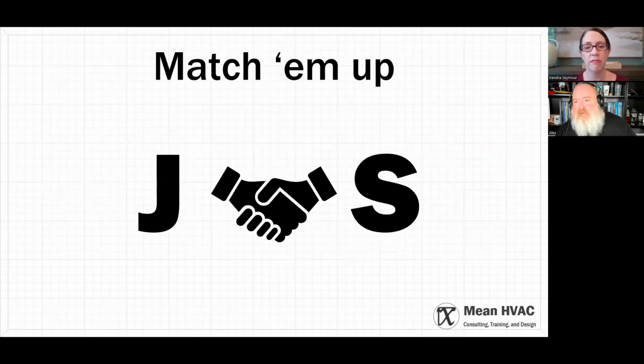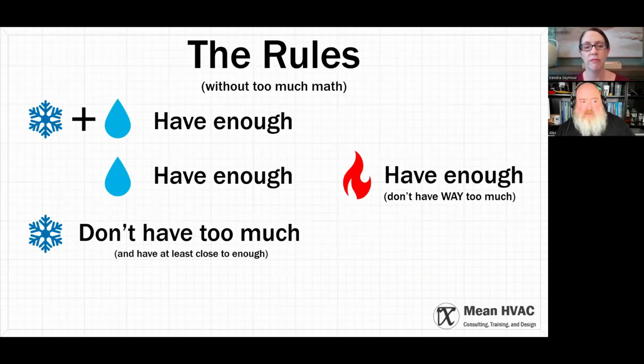So the job is to match them up, and the rules are fairly simple. You got to have enough of your temperature control and moisture removal, right? You got to have enough moisture removal, period. The trick is not having too much temperature control. Too much is bad. Bigger is not better. I'm going to say that again: bigger is not better.